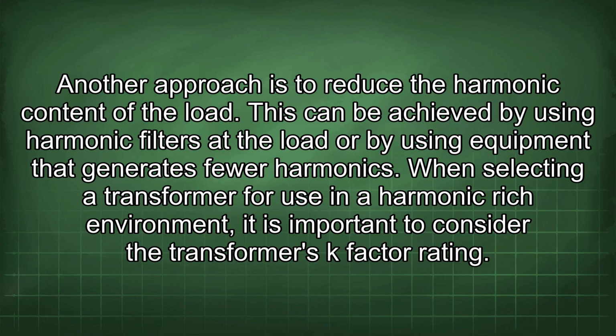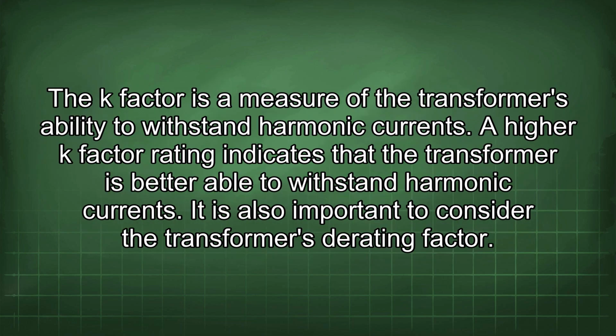Another approach is to reduce the harmonic content of the load. This can be achieved by using harmonic filters at the load or by using equipment that generates fewer harmonics. When selecting a transformer for use in a harmonic-rich environment, it is important to consider the transformer's K-factor rating. The K-factor is a measure of the transformer's ability to withstand harmonic currents. A high K-factor rating indicates that the transformer is better able to withstand harmonic currents.